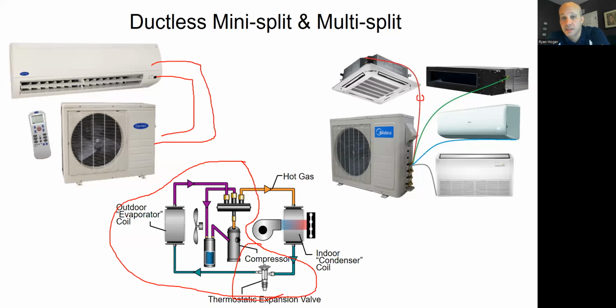Both lines get insulated. The idea here is you can locate different zones. So like maybe I have 4 offices next to each other, and each person wants to have their own individual control. They're all very important people. They can't possibly share a thermostat. You could give them each one of these heads, right? And they can each have their own little handheld control or wall thermostat that they use independent of each other. And this is just showing you different kinds, right? I could have 4 of these cassettes, right? Or I could have 4 of these high walls, right? Or I can mix and match them. It doesn't matter for most manufacturers. So that way individual control can be had in each room.